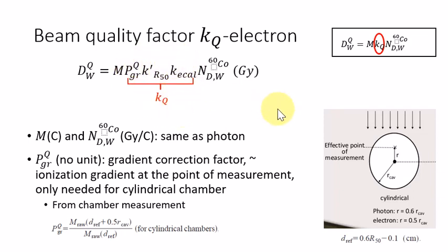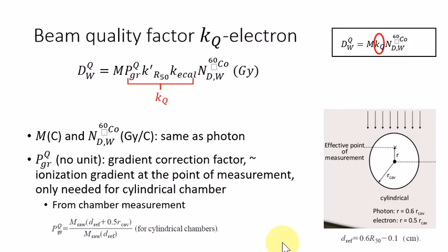The KQ factor equals the P gradient multiplied by the KR50' multiplied by the KECAL factor. The first factor is the P gradient. It has no unit. The P gradient is the gradient correction factor.